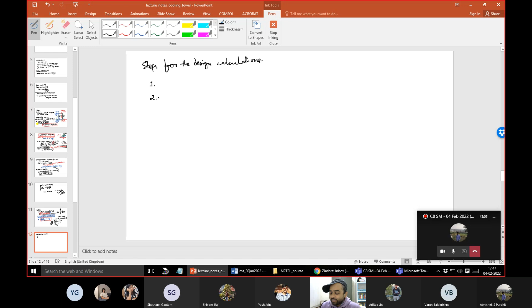So you should design your tower such that it can give the designed performance, or the rated performance, at the worst condition, and the worst condition is the high humidity season. Right? After you do this, the third step is to draw the equilibrium curve, the enthalpy temperature curve, and this is nothing but the 100% saturation line that you get from the psychrometric chart. Right? For 1 atmospheric pressure, this equilibrium data is always with you in the form of the psychrometric chart.